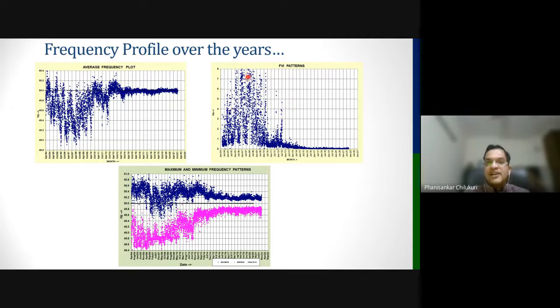Similarly, this is one metric which we track. This has also settled down to zero. The ideal frequency variation index that we track should be zero. And the maximum and minimum frequencies earlier used to vary widely between 48.4 and 50.51. But now the Indian grid frequency stays in a very narrow band, and our target is to bring it as close as possible to 50 hertz to ensure reliability of the grid.